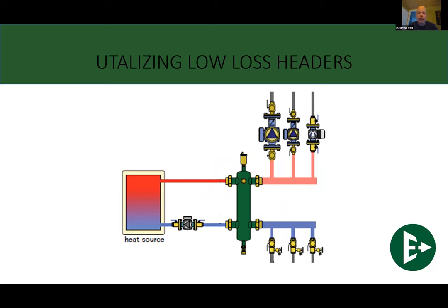Now I love these things. They are my favorite piece of hydronic system nowadays. And I'll tell you why. Number one, it takes that boiler that you just put in, that $10,000 boiler, $5,000, $8,000, whatever it is, and it makes it its own system. It sees the flow it wants to see. It sees nothing of the system. It doesn't care what the system's doing. It just takes care of your boiler.